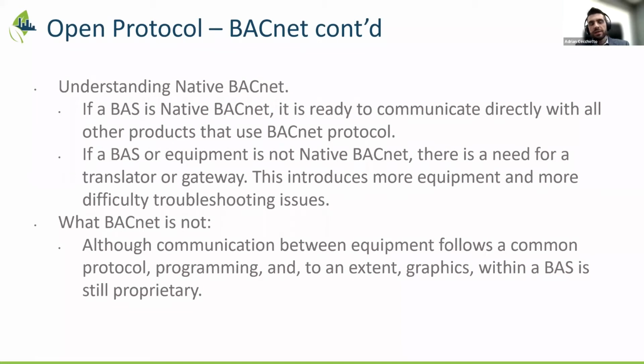Laggards, I'd say sometimes things like certain boiler manufacturers, other smaller pieces of equipment too, where it's almost like they're offering a BACnet gateway just to meet a spec requirement as opposed to actually engineering a proper solution. So sometimes that can get in the way.